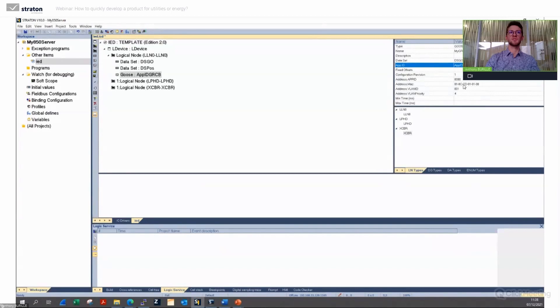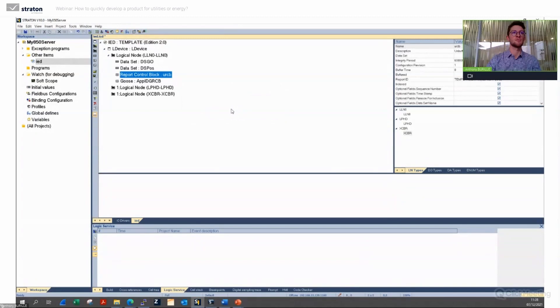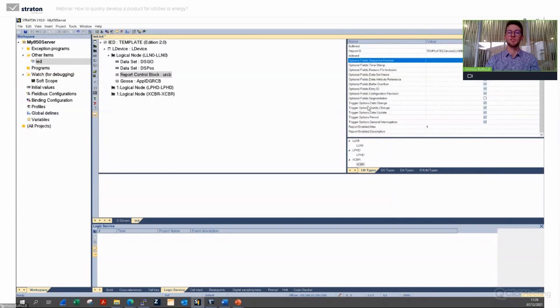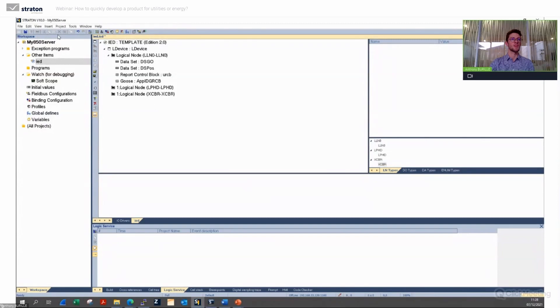I choose a name, description, a dataset — here I take the dataset for GOOSE — and an App ID. There are also parameters from the standard. I then add a new report control block to communicate the circuit breaker position — either buffered or unbuffered, it doesn't matter for this demonstration — linked to the Position dataset, with optional fields, trigger options to send the report, and so on. If I have any doubts about my configuration, there is a Check Syntax button to verify the whole SCL file against the standard.